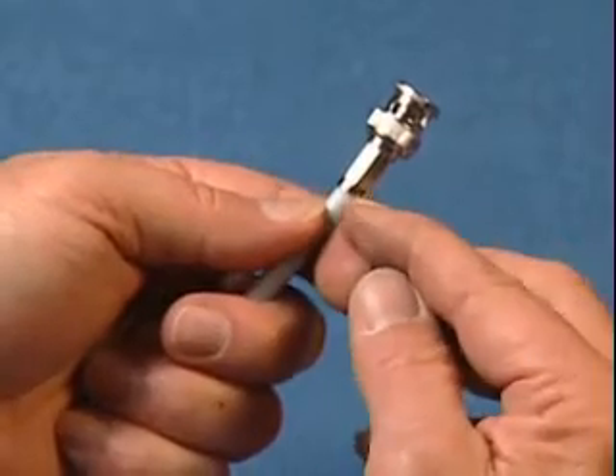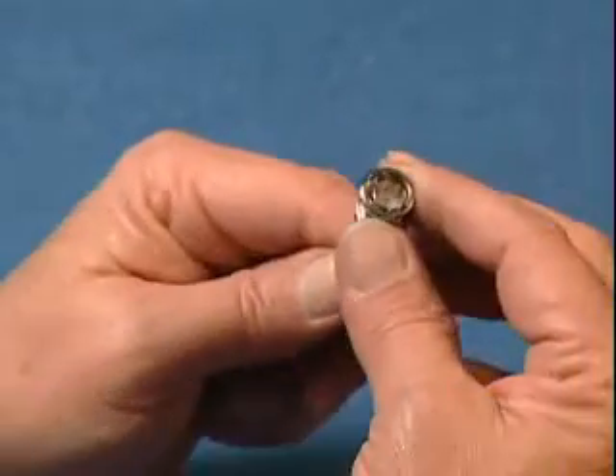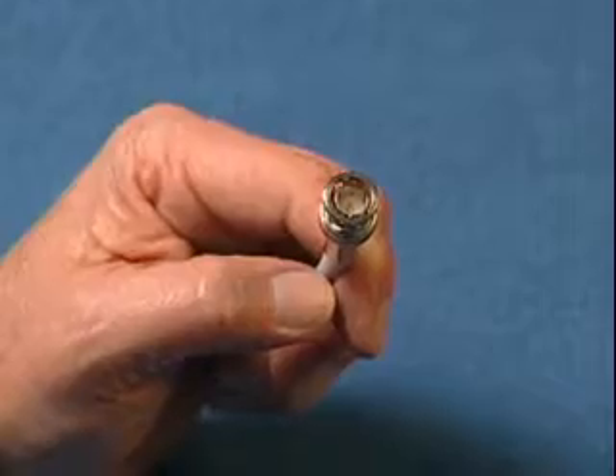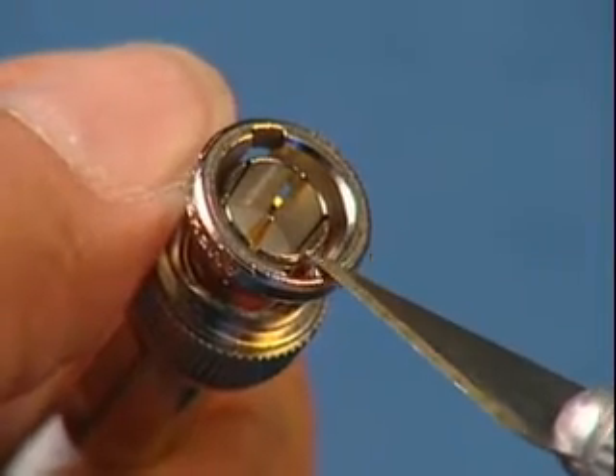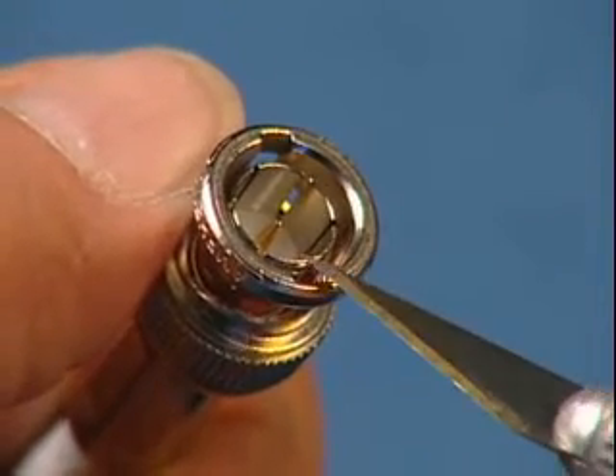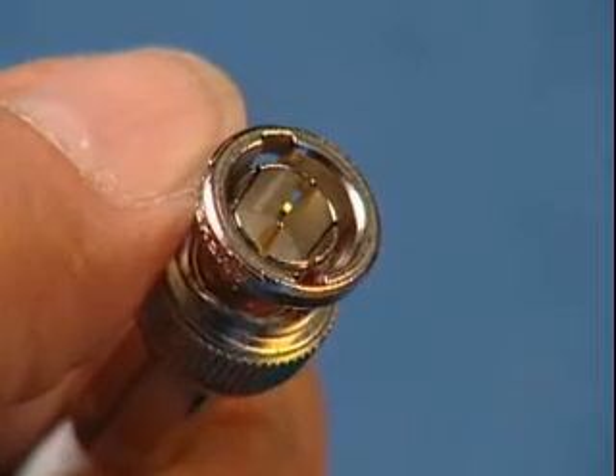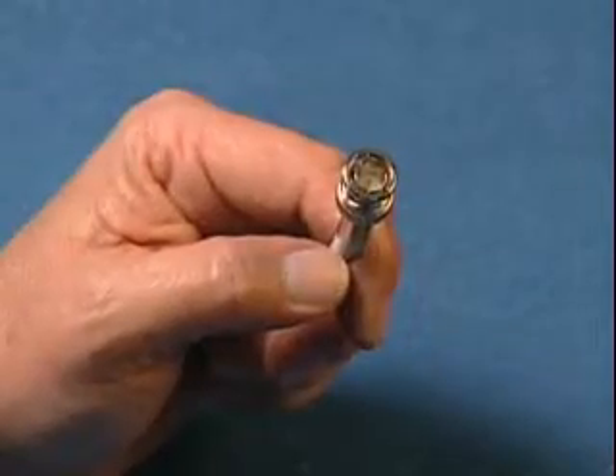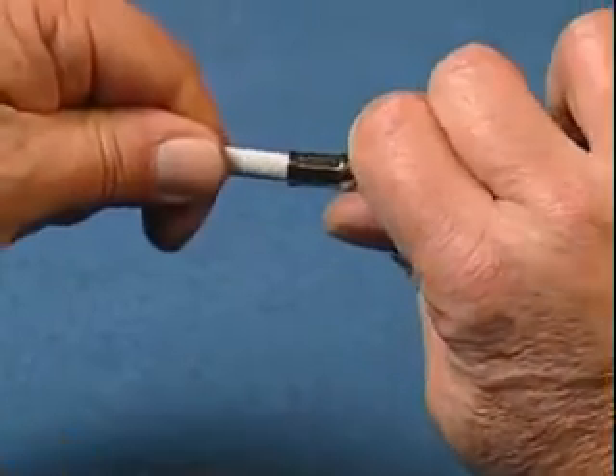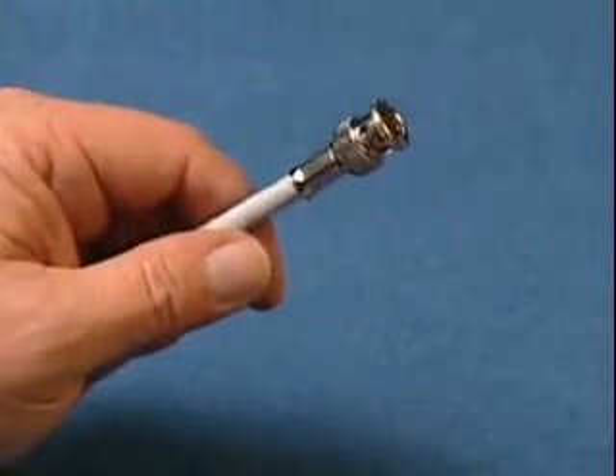The crimp should extend to the bottom of the connector body and not the cable end. The center pin should be flush with the inner ring of the connector. A properly crimped connector will not pull off the cable. This connection is now ready for testing.